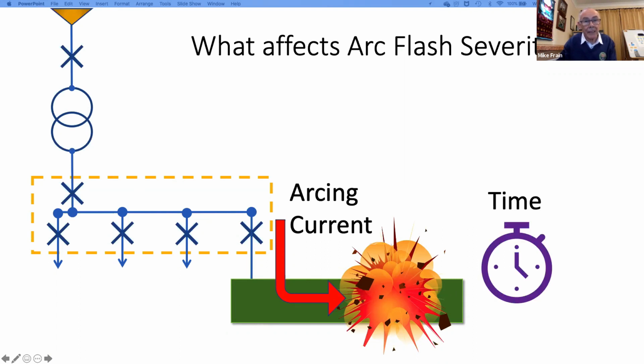The other factor is time. Arcing current we can't do a lot about, but time we might be able to do something about, because that's worked out from the protective device at that point, which supplies that piece of equipment. So again, the incident energy level is directly proportional to time. So if we halve the amount of time through lowering the protective device settings there, it'll lower the incident energy level by a half.